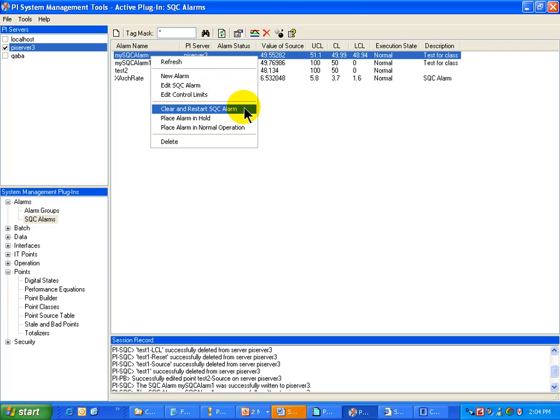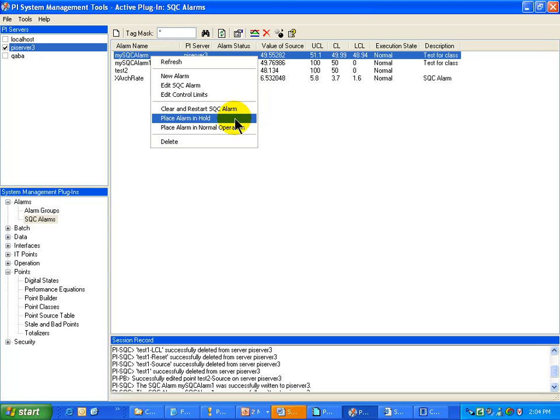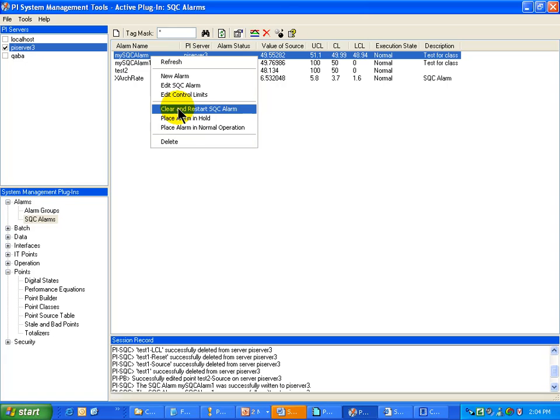I can also clear and restart these SQC Alarms, place the Alarm in Hold, or put it in Normal Operation. If you recall, that was the behavior that is controlled by the Reset Tag. That Reset Tag has a value of 0, 1, and 2. It is a digital value itself, and this is the client application that manipulates it.